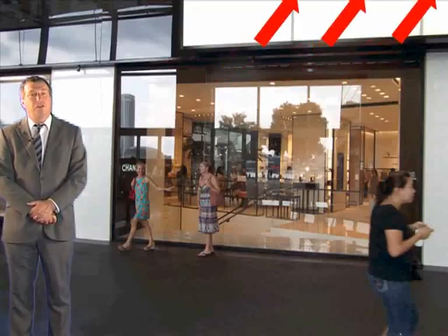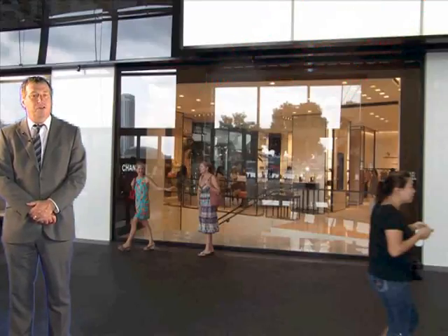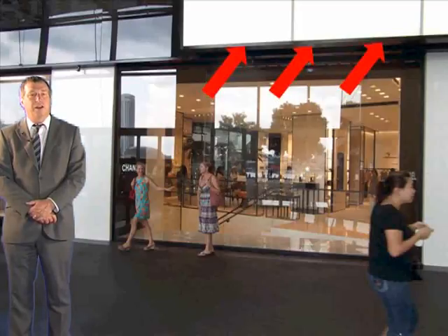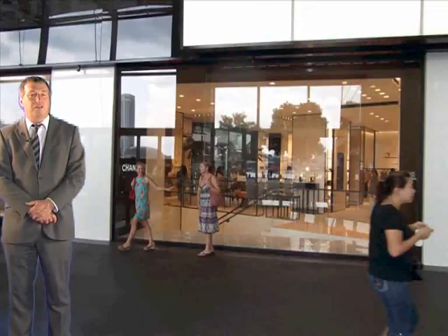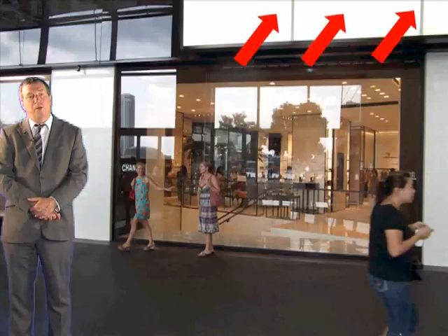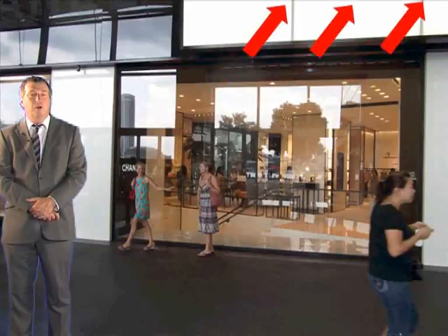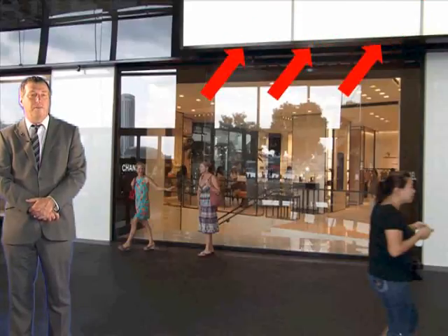Another way that smoke might be extracted without letting it spill into a smoke reservoir in an atrium would be through the use of slot extraction. Slot extraction requires no screen to stop the smoke spilling out or up, but it merely extracts the air-smoke mixture at such a high rate that no smoke can get past the slot. Slot extraction would normally be found at an opening. Perhaps, for example, the building designers do not want smoke to leave a shop into the atrium, but want the smoke to be extracted at the shop front instead.